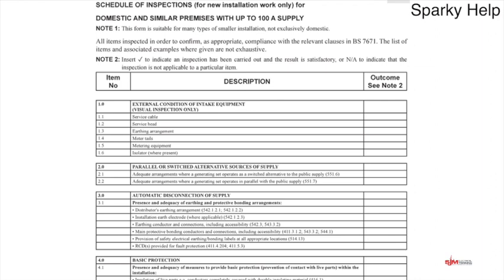So we've got one schedule of inspections, and we've only got one distribution board in our made-up example, so we're going to put one schedule of test results. In a large building, you could have many schedules of test results because you're probably going to have one per board, so that would be a large number. So what does the schedule of inspections look like? Not that this is the video for this, but that's it. It's the tick box. Apparently the chances are this is going to be shortened down for the new regulations. But in here we are basically looking to put in either a tick or an NA against anything on the description that is relevant to the project or installation that you are inspecting yourself.